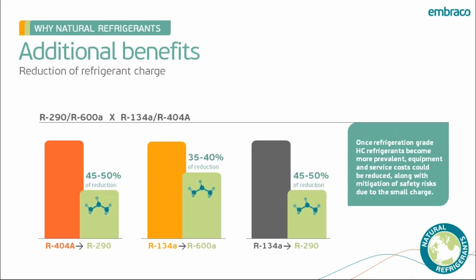So what makes a refrigeration grade hydrocarbon? Well, it has a high level of purity and a low level of moisture or other contaminants. Now the odorant is removed because this is considered a contaminant. And we want to look for proper labeling to ensure that the gas can be used in a refrigeration system. For example, refrigeration grade propane should be labeled R290 and should not have a blue rhino in the tank. Let's save that one for the burgers.